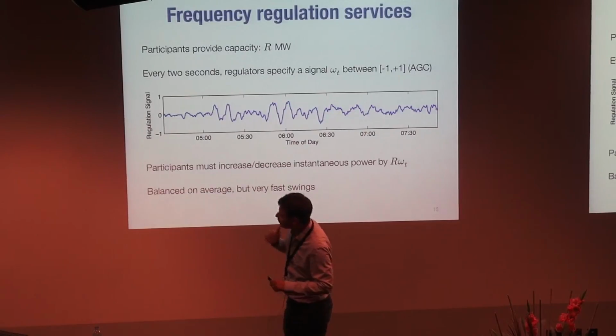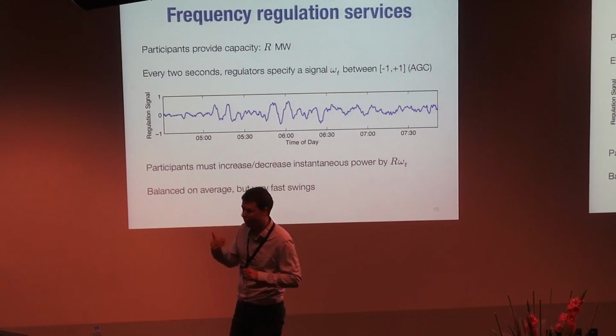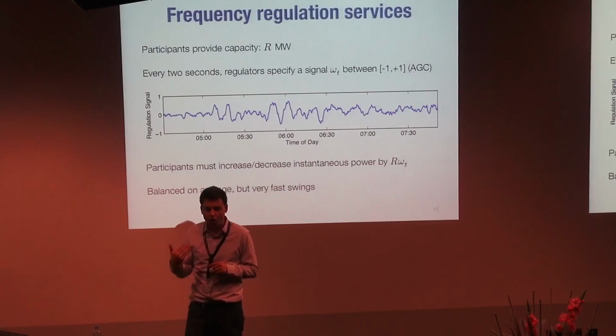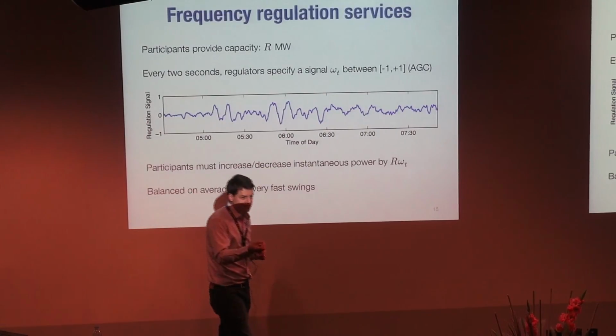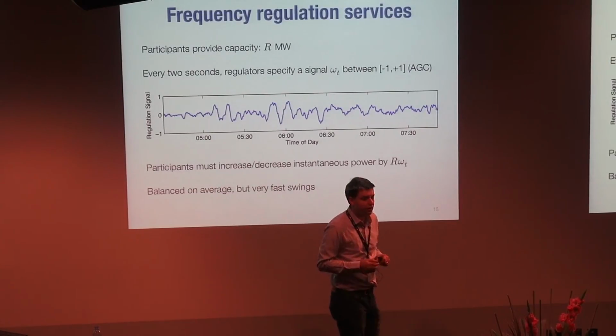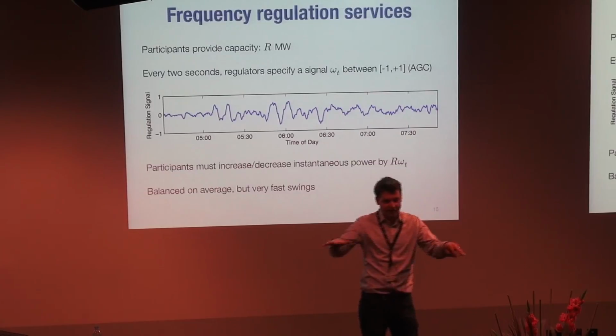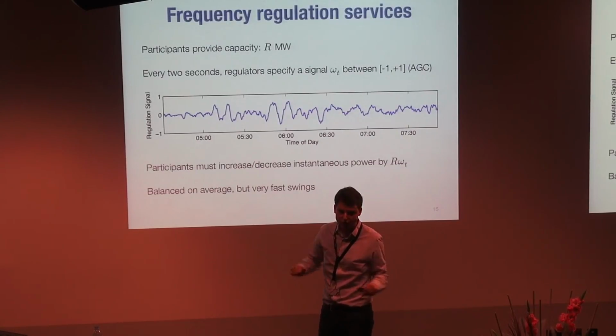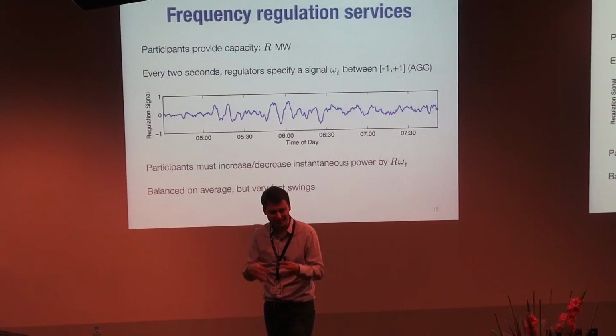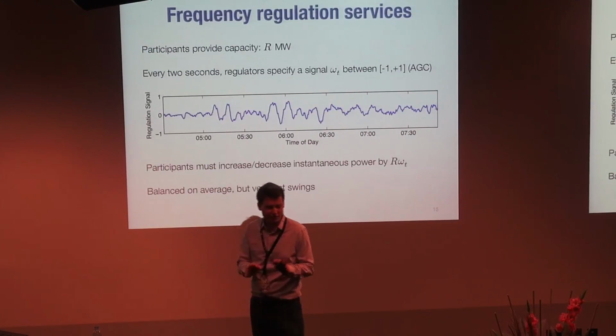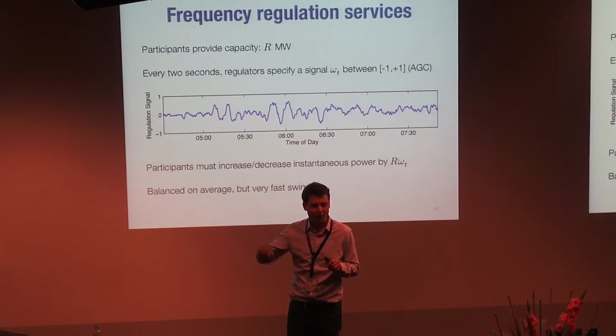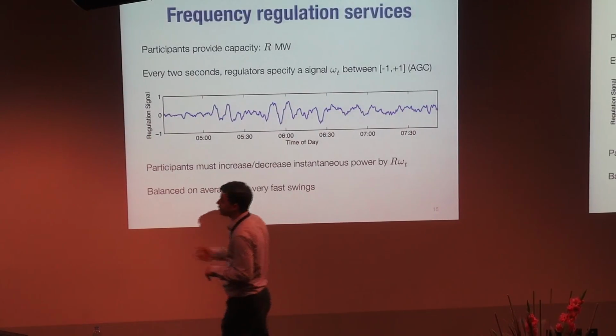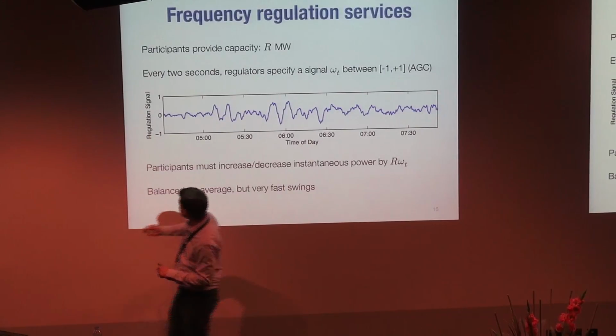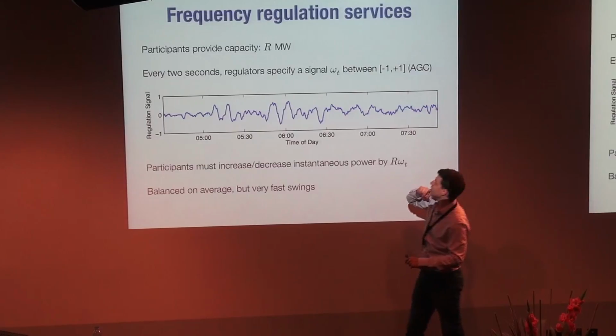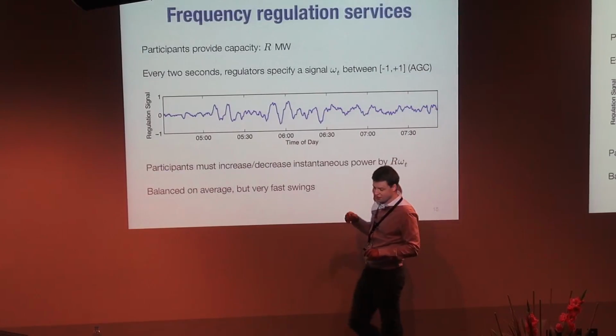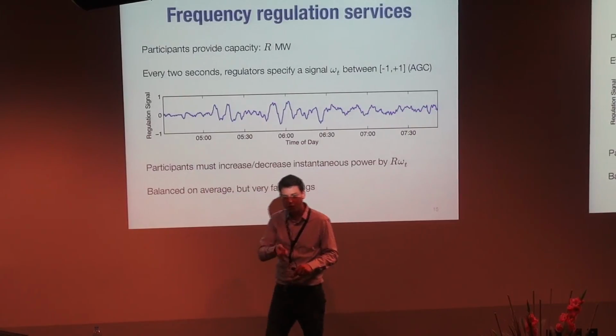The idea is that each participant in this service provides some capacity, which I'll call R megawatts. Every 2 seconds, the frequency here is a 2-second update, the system operator will broadcast some global signal to everyone. So we are assuming you have at least some communication that is somewhat reliable, because that 2 seconds is even quite a bit slower than how we reacted before. This is why it's called secondary frequency regulation, whereas the first one is primary frequency regulation. Every 2 seconds they specify some signal, which I'll call omega T, using maybe bad notation. It's essentially a signal that is dimensionless, but it varies between -1 and 1.